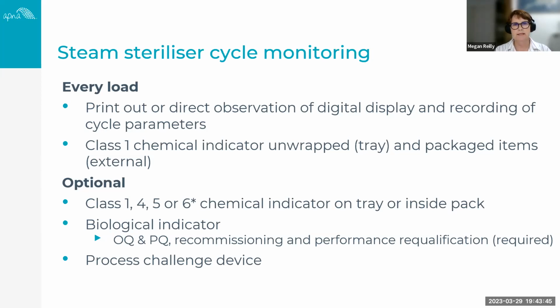Now, the standard does say that any other sort of chemical indicator inside the pack, so 1, 4, 5, or 6, is optional. Some people like to do it because it's an extra evaluation of the process. Your biological indicators are required at operational qualification and performance qualification, on recommissioning and performance requalification if that is indicated, if you've had a problem with your sterilizer. But again, you're talking with your service provider in relation to this.